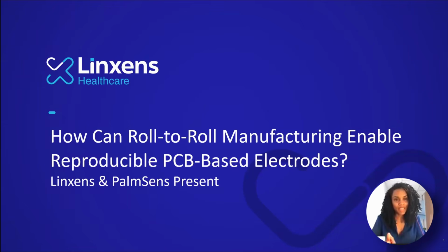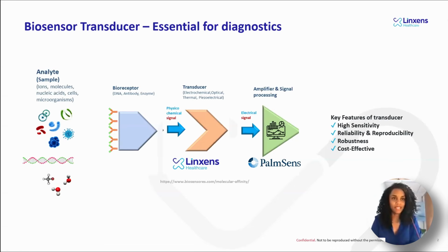So before exploring how R2R manufacturing can provide reproducible PCB-based electrodes, I think a good point is to revisit the basics of the biosensor system to understand where the Linxens offer is. In the system of biosensors, you have an analyte. This analyte reacts with a bioreceptor, and this bioreceptor reacts with a transducer, and this transducer will transfer an electrical signal to an electrical device. This electrical device can be a potentiostat, like those from PalmSens, and Linxens will provide the transducer.